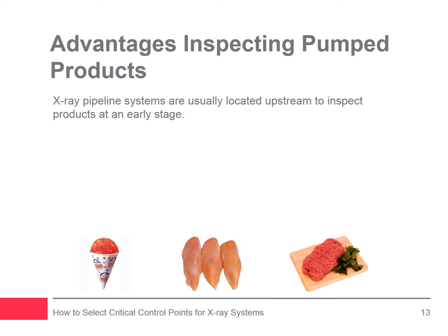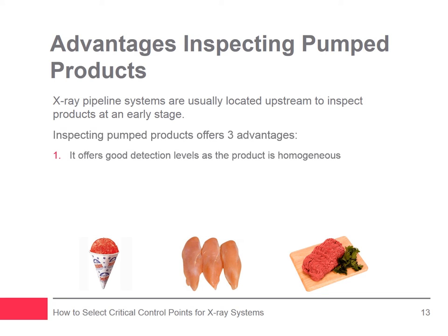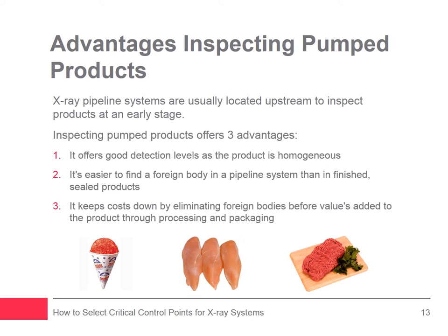Pumped products are typically slurries, semi-solids, and fluids before final packaging. Typical applications include sauces, jams, minced meat, whole muscle, chocolate, fruit puree, dairy spreads, and pharmaceutical slurries. Like bulk machines, an x-ray pipeline system is usually located upstream to inspect products at an early stage. It offers very good detection levels because the product is homogeneous and usually pumped through an inspection manifold that's 50 millimeters deep or less. It's much easier to find a foreign body in a pipeline system than in finished products such as glass jars, and it keeps costs down by eliminating foreign bodies before value is added through processing and packaging.